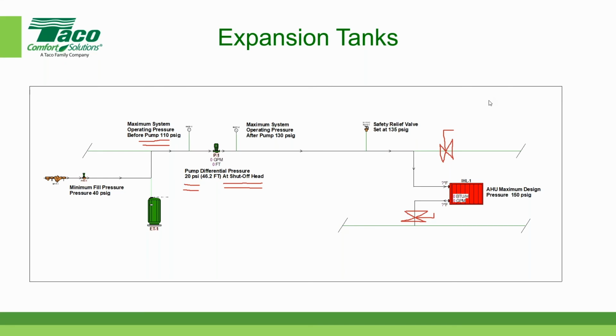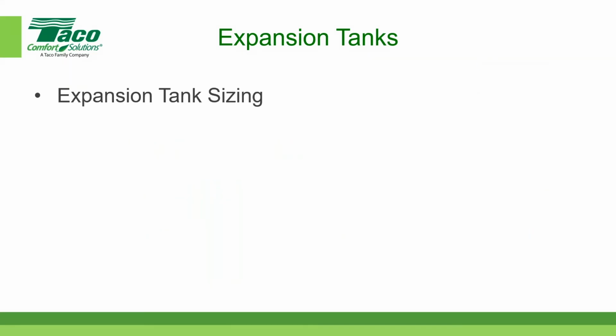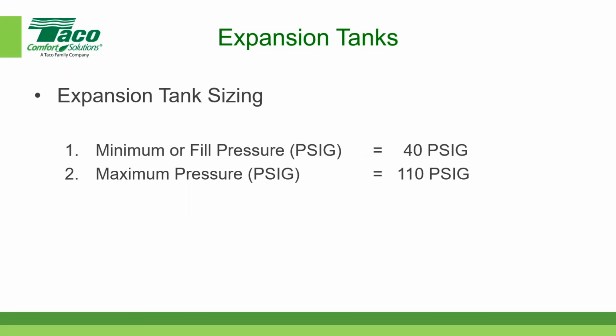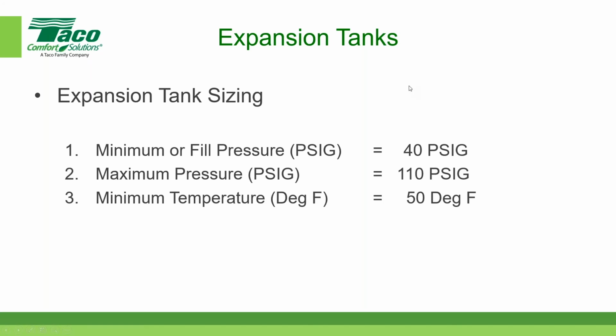All right. So moving right along, as they say, we now know the minimum or fill pressure. We now know the maximum pressure at the expansion tank. The next thing we want to determine is what is the minimum fill temperature. And in this case, I happen to live in New England in the States, and our groundwater temperature is pretty constant at around 50 degrees Fahrenheit. So if I'm taking water from a well, I happen to have a well at my home, and I know that water temperature is around 50 degrees year round, and that would be the fill temperature of the system. And if it's a municipal water supply, that piping is underground, so it's also at 50 degrees Fahrenheit.